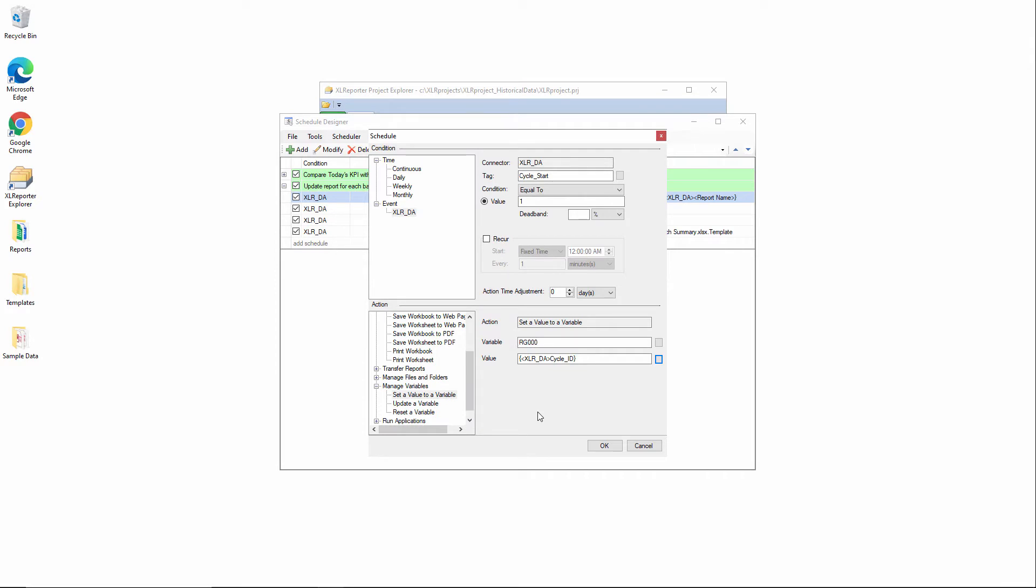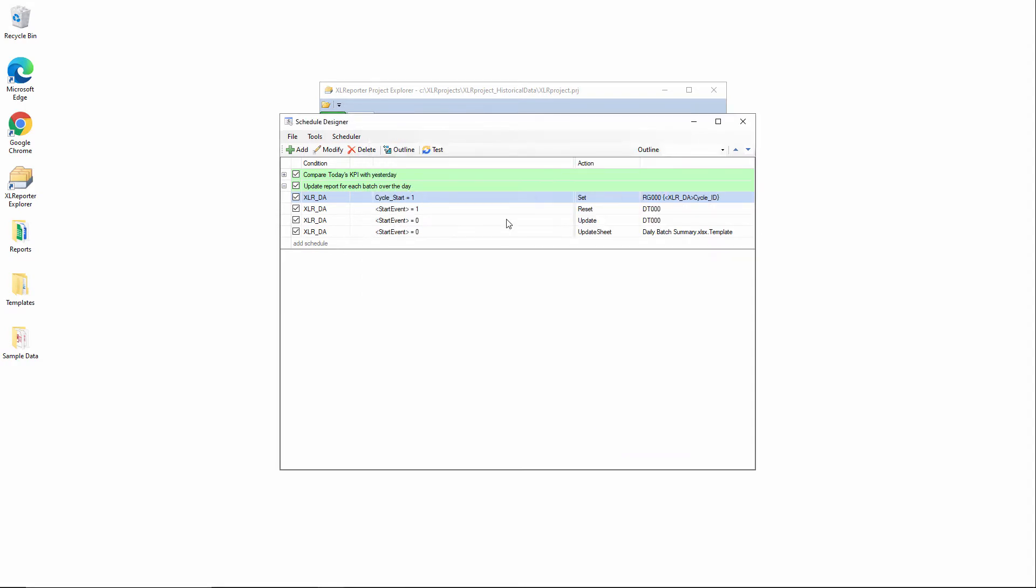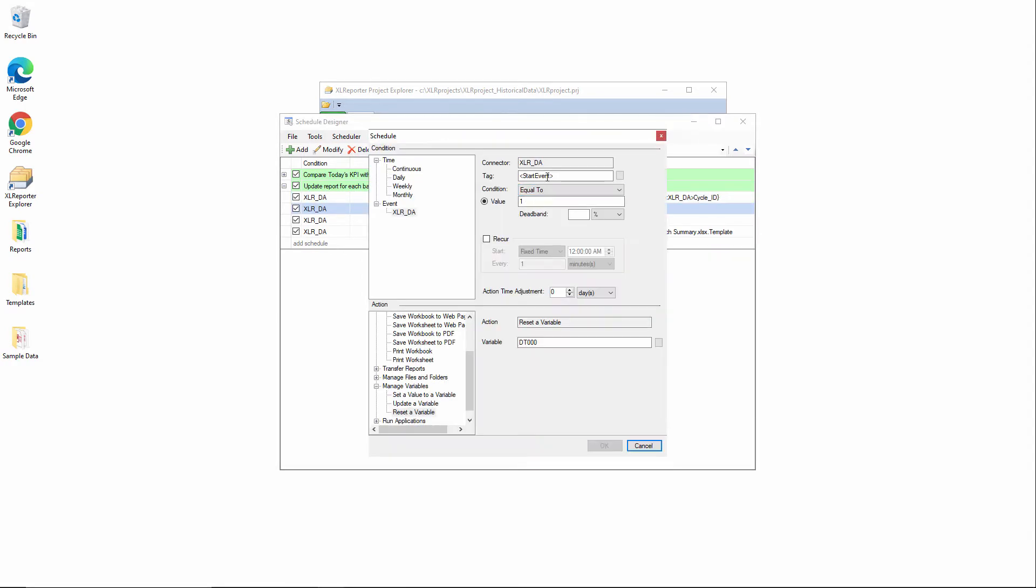Once again, just to reiterate, when the cycle start tag transitions from a value of zero to one, we'll capture the value of the cycle ID tag in the PLC and stick it in this internalized XLreporter variable. Now also, when the event starts, we will set the start time on this date and time XLreporter variable. Think of this sort of like a stopwatch that lets you see the start and the end and the duration of an event. Here we're getting the start time.